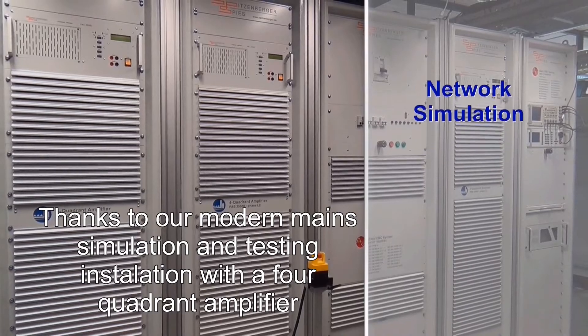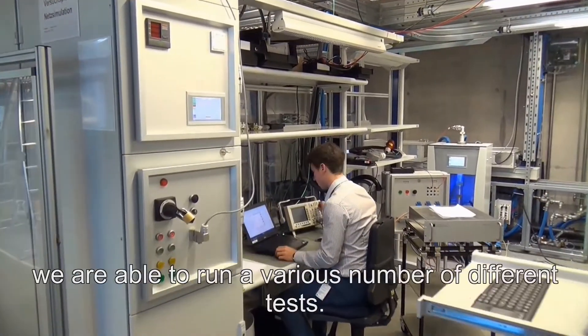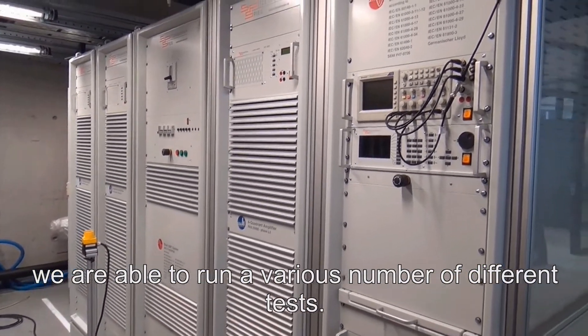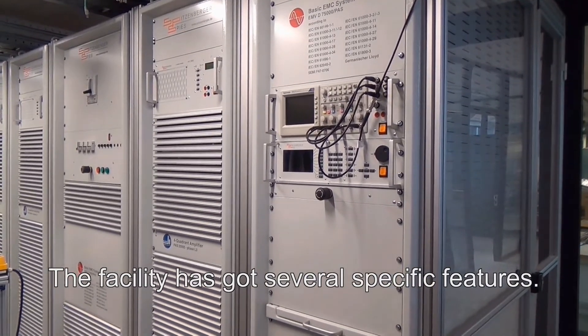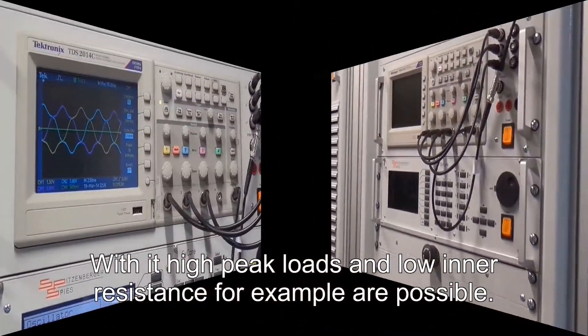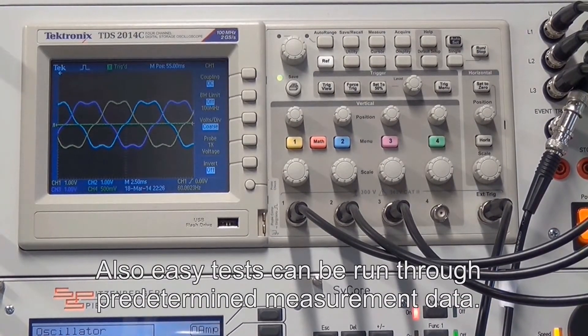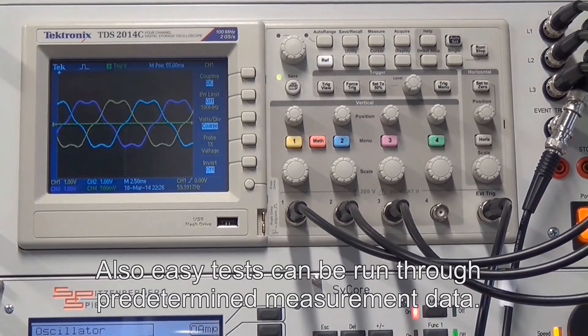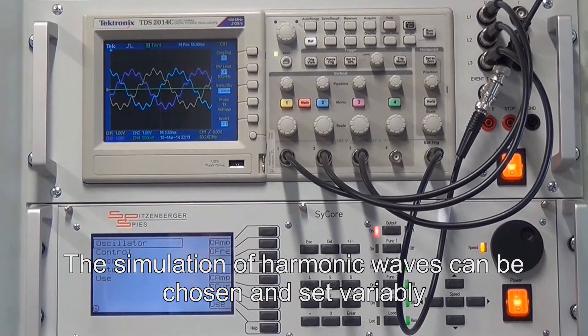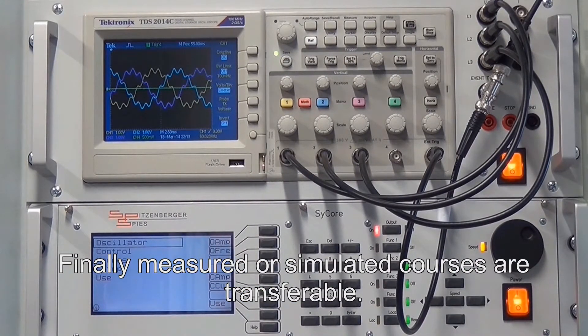Thanks to our modern mains simulation and testing installation with a 4-quadrant amplifier, we are able to run a various number of different tests. The facility has several specific features: high peak loads and low inner resistance are possible, easy tests can be run through pre-determined measurement data, the simulation of harmonic waves can be chosen and set variably, and measured or simulated courses are transferable.